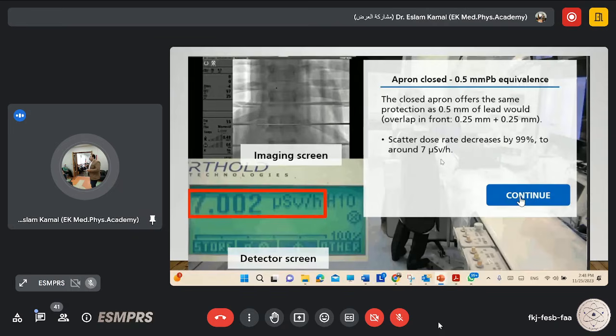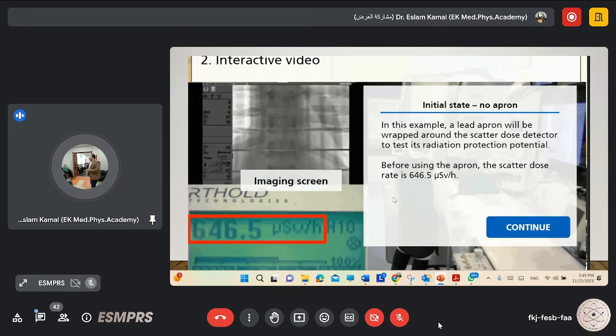As you can see here, if you want to measure the efficiency of the lead apron itself, we cover the radiation detector with the lead apron, and you will get a dose of around 7 microsievert per hour. While not using the lead apron, you will get a dose of around 646.5 microsievert per hour. That means the lead apron will reduce the radiation exposure to our staff during the fluoroscopic procedure by 99%.